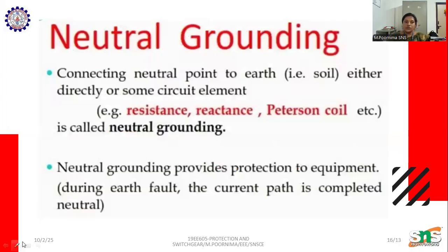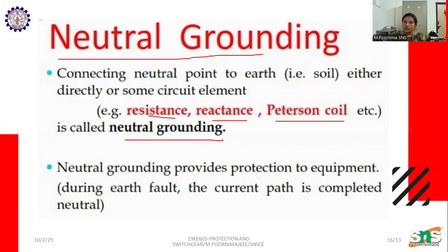So here comes neutral grounding. Neutral grounding is connecting the neutral point to the earth, that is the soil, either directly or through some circuit elements, for example resistance, reactance, Peterson coil, etc. That is called neutral grounding. So neutral grounding provides protection to the equipment. During an earth fault, the current path is completely through the neutral.